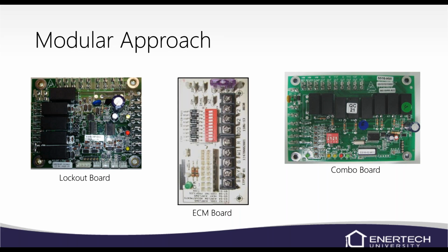The board's pretty cheap. I would say it's probably somewhere around 40 bucks. So it's relatively inexpensive, unlike some of our older double stack boards, where the ECM board and the lockout board were all tied into one, and it might be $400 or $500. Our lockout boards are pretty cheap, and to be honest, they're pretty reliable too. So we don't have a lot of lockout board failures. I'm not saying they don't fail, but we don't have a whole bunch of them that fail often. So that's a pretty good lockout board.